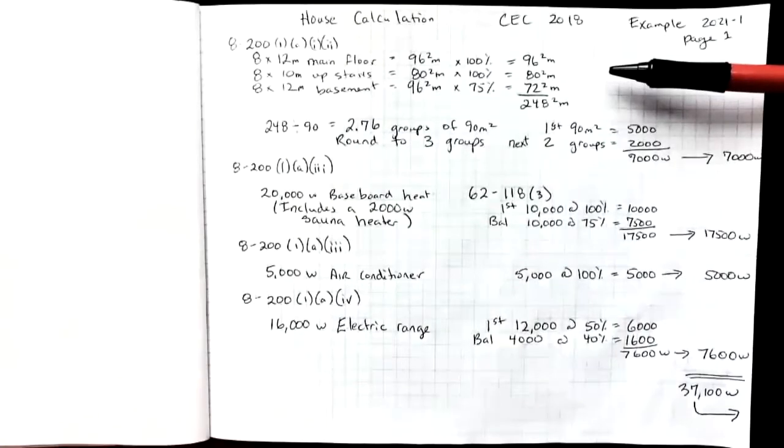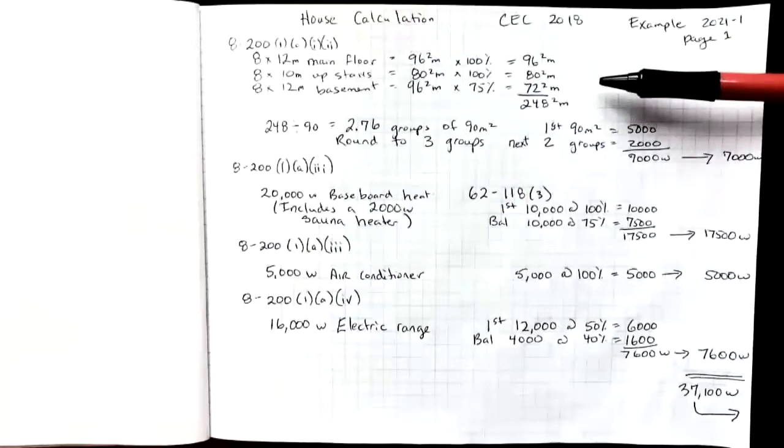Also we'll look at the ground wire size. Okay, so using rule 8-200, we're going to first find the demand for what's called our basic load using the area of the home.